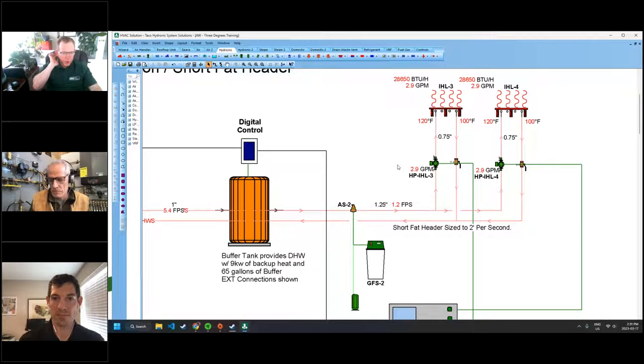This application with that tank you saw earlier, I'm happy with how this would be piped because I know the hottest water is going out. But to Bob's point, if you had a different style buffer tank, you don't actually know what water temperature you'd be delivering here. You could be delivering 80 degree water when your heat pump is actually putting out 120 degree water. And that's sort of where Bob is leading to. And good news is, Bob, we got a drawing for that as well.